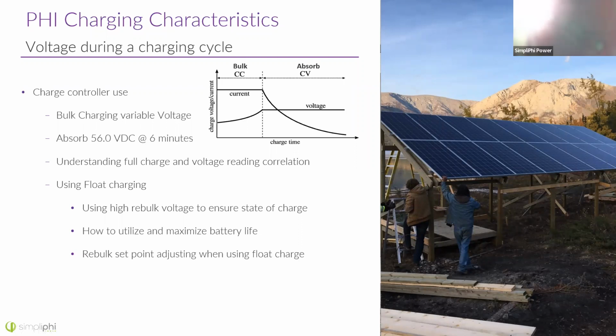There's an additional float process that can occur, and float occurs at 54 volts. You would only typically float batteries if you have a renewable energy source where you're not paying for the fuel to float the batteries. And that's to try to keep the batteries topped off. So if you're using float charging, you're going to try to keep the batteries topped off.